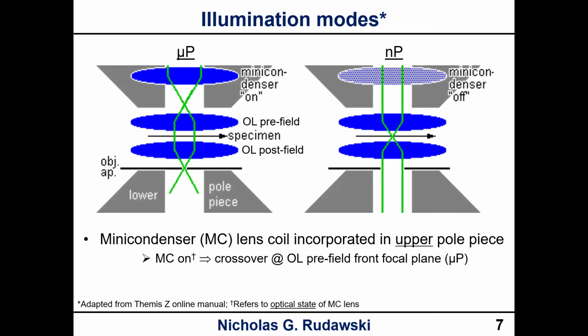If you're in what's called nanoprobe mode, the mini condenser lens is off, and then you don't have the crossover. So then your beam enters your objective lens pre-field mostly parallel or nearly parallel. What you end up with is your beam getting focused to a point on the sample. It's important to note that when we say on versus off, that doesn't mean that there isn't current going through the coil when it's off. That specifically means that the lens is optically off.